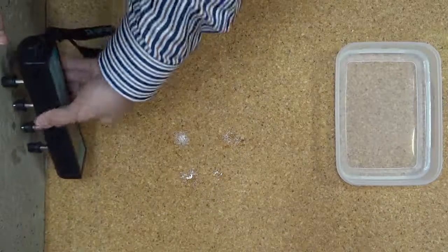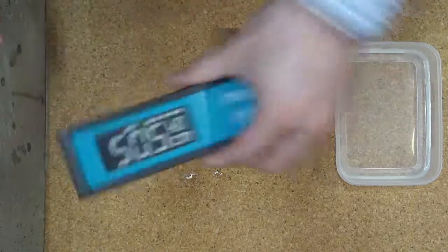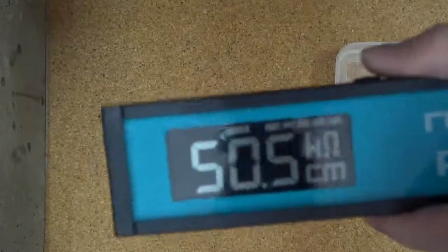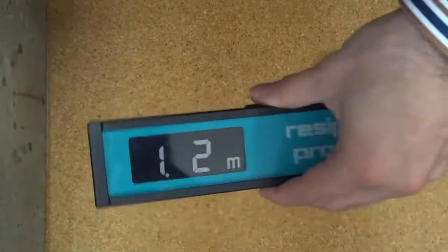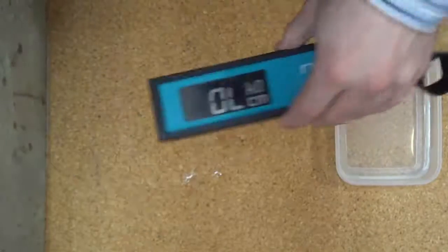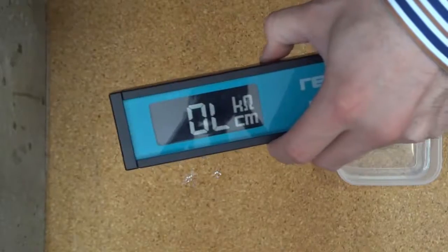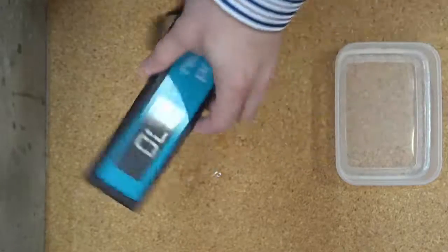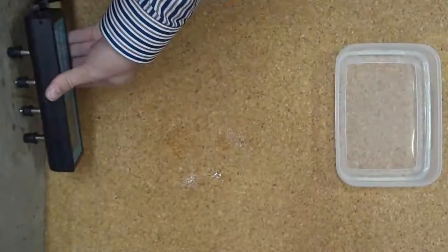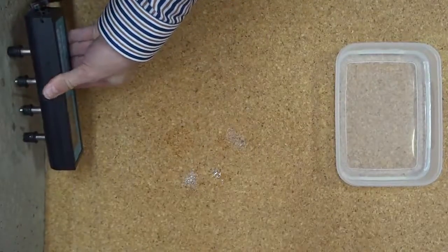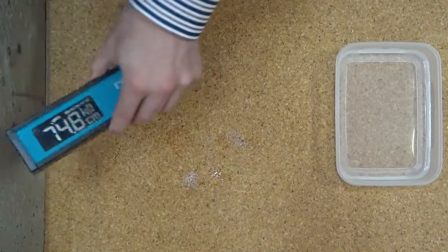To record further records in the same file, continue the same process, pressing the top hold button, then the bottom save button. To change to a new file, turn the Resipod on and we have moved now to file two and have taken record one.